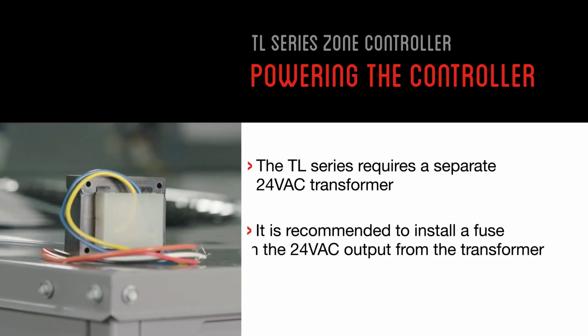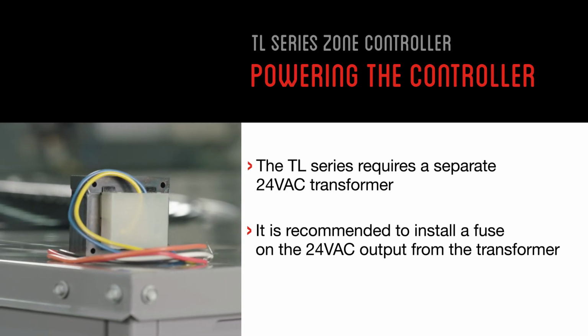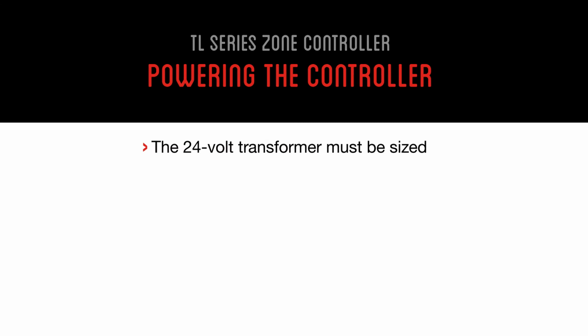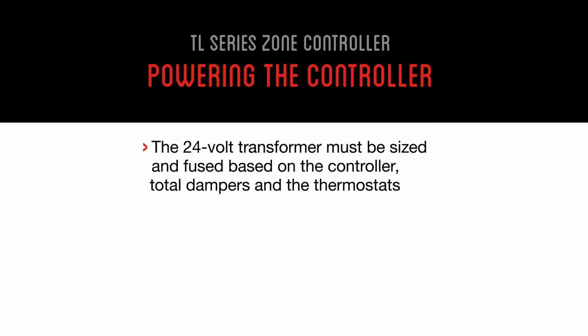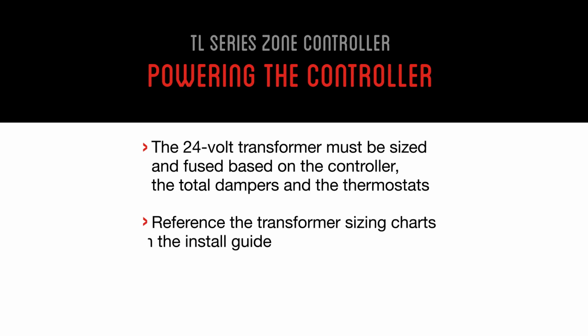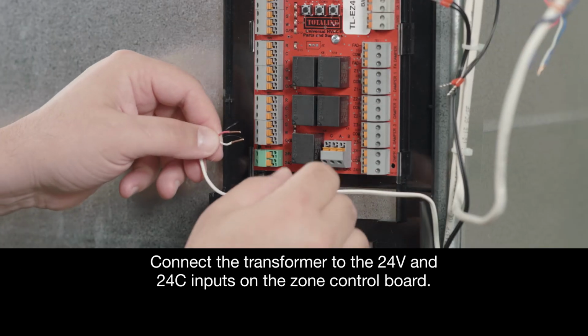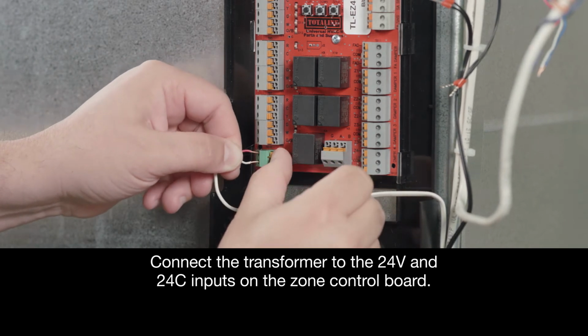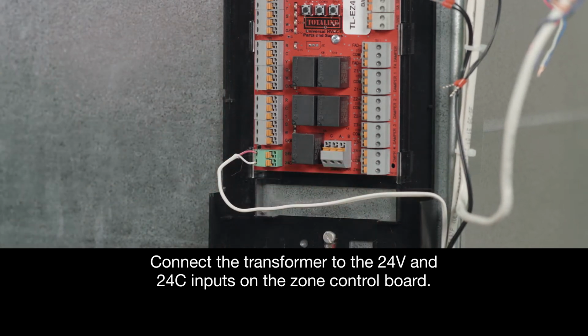It is recommended to install a fuse on the 24-volt AC output from the transformer. Note that the 24-volt transformer must be sized and fused based on the controller, the total dampers, and the thermostats. Reference the transformer sizing charts in the install guide. Next, we'll connect the transformer to the 24V and 24C inputs on the zone control board.